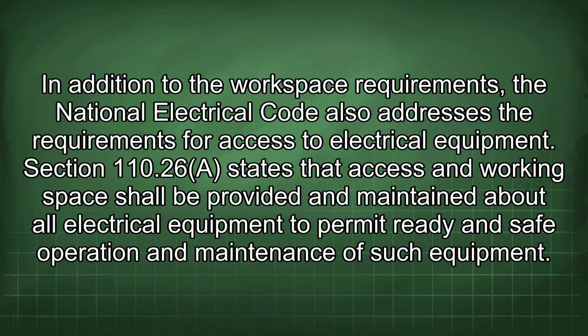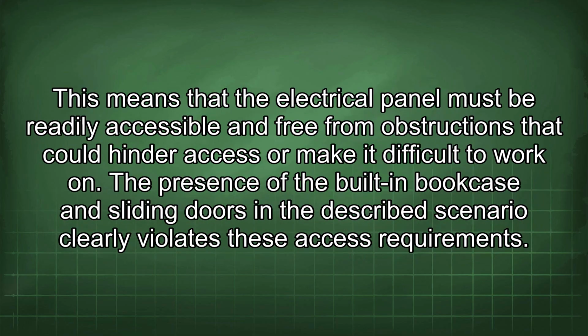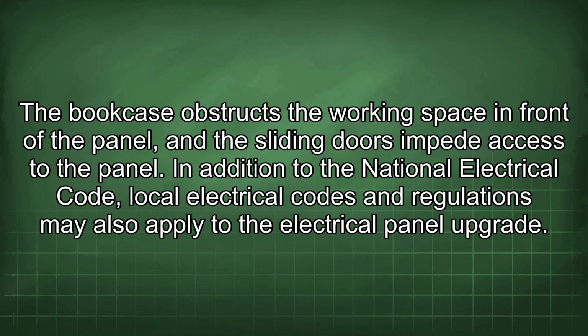In addition to the workspace requirements, the National Electrical Code also addresses the requirements for access to electrical equipment. Section 110.26 states that access and working space shall be provided and maintained about all electrical equipment to permit ready and safe operation and maintenance of such equipment. This means that the electrical panel must be readily accessible and free from obstructions that could hinder access or make it difficult to work on. The presence of the built-in bookcase and sliding doors in the described scenario clearly violates these access requirements. The bookcase obstructs the working space in front of the panel, and the sliding doors impede access to the panel.